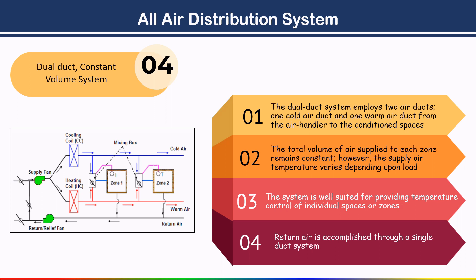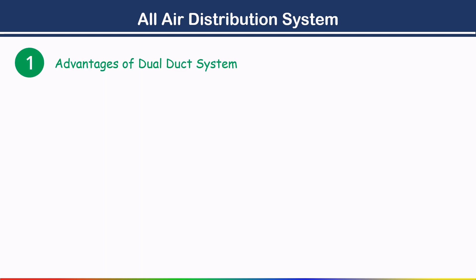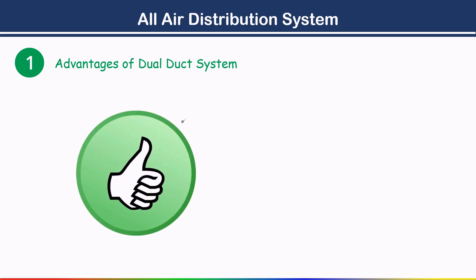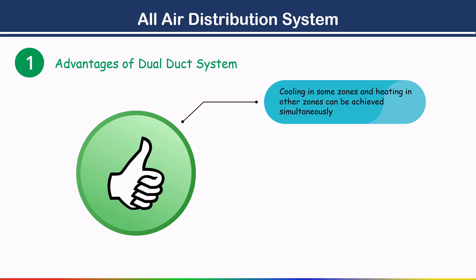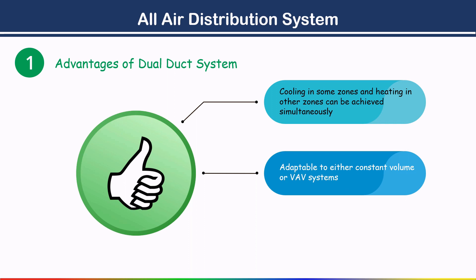Advantages of the dual duct system: First, cooling in some zones and heating in other zones can be achieved simultaneously. Second, the system is adaptable to either constant volume or VAV operation. Third, no seasonal changeover is necessary.